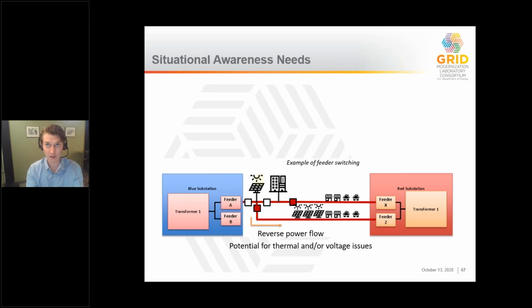Studies don't always account for these contingencies, because there can be so many, even for just a set of two substations, that with current tools and methods it's not always practical to study all the configurations. That leads to a need to monitor the voltage, power, and current output at these different locations, to have awareness of whether reconfiguring the system creates a voltage or thermal issue from DER, which we want to keep online even in abnormal configurations to the extent possible.